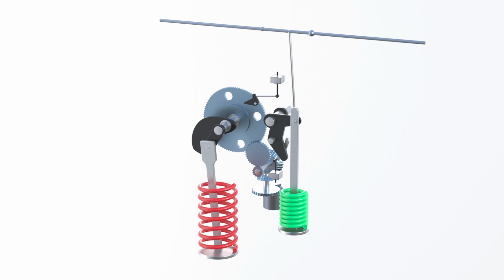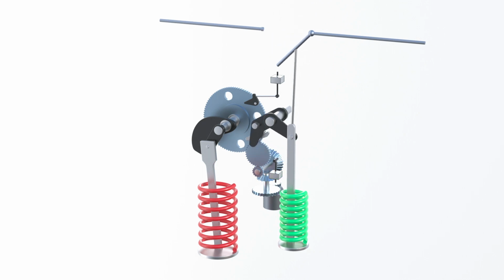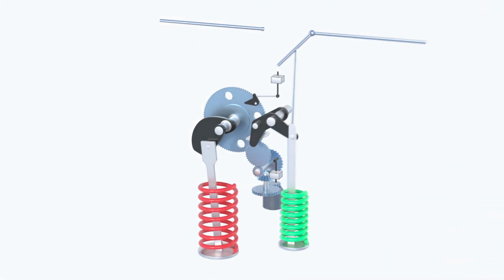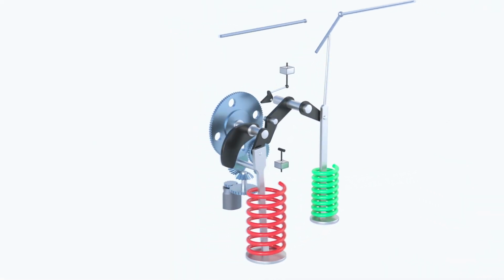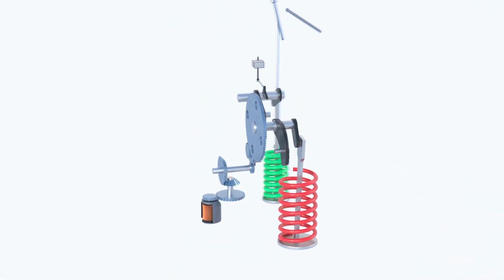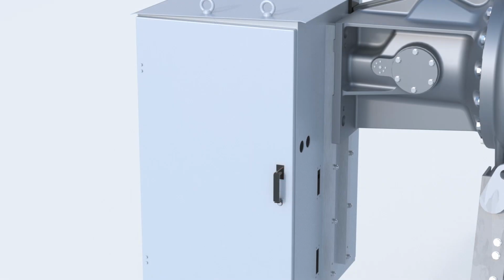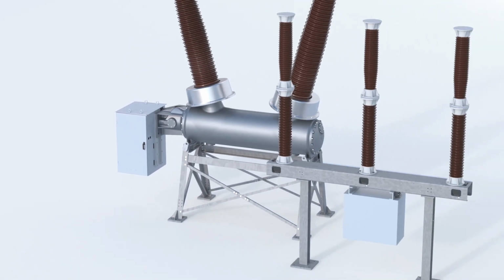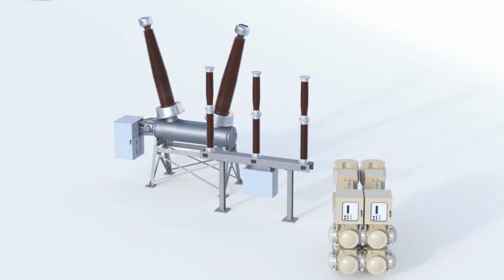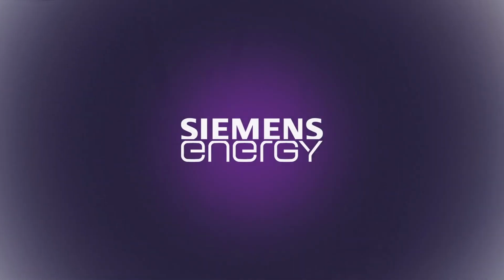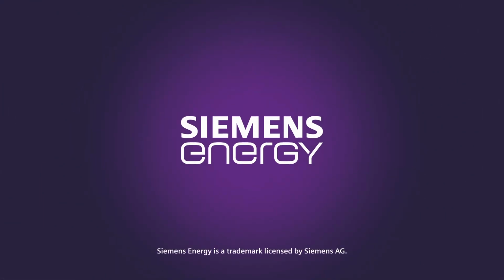After terminating the opening operation, the closing spring can be actuated immediately on demand. This process charges the opening spring. Therefore, an opening switching operation can be triggered again immediately. A virtually maintenance-free design and a low number of moving parts ensure safe and reliable operation for decades.